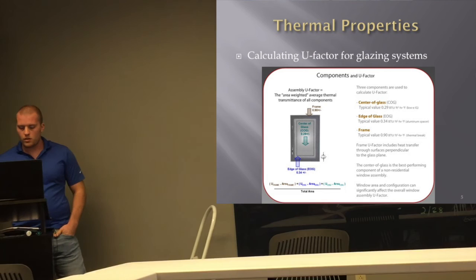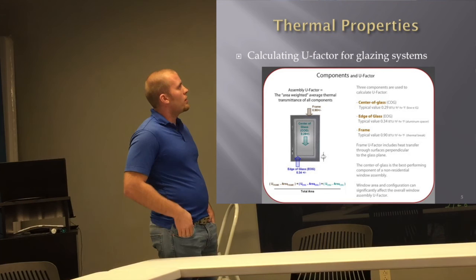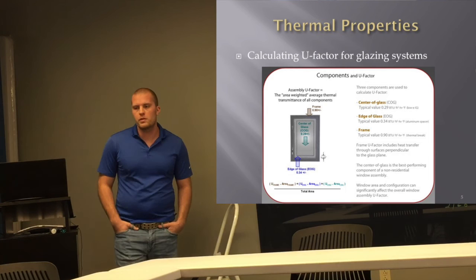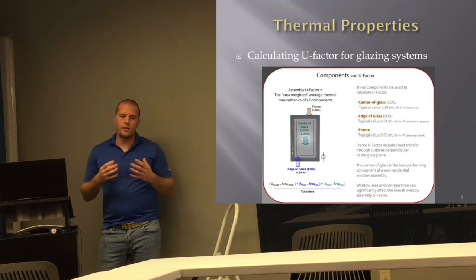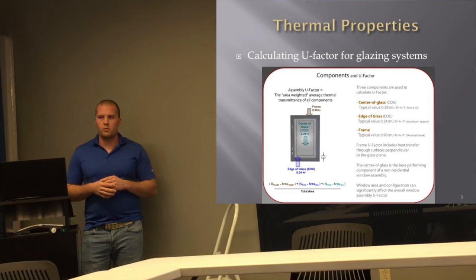The U-value is not unitless — it's BTU per square foot per hour per degree Fahrenheit. Solar heat gain coefficient is unitless, and condensation resistance gets a unitless rating in Window. The U-value is the only one with units, and it's basically the inverse of an R-value, so if you're more familiar with R-value, it's just the inverse of that.